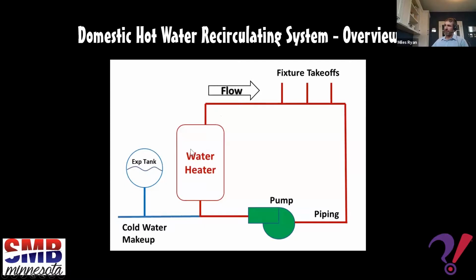Well, we have a water heater here that is creating hot water, maybe 140 degrees, 130 degrees, sending it out into this pipe. But now we'll create a loop. We have a piping loop with a pump on it, a recirculating pump, that basically makes sure we have hot water available in this piping loop at all times, because we'll have takeoffs from that piping loop to the various fixtures, the various showers, the various faucets. And we want all of the users of those fixtures to have hot water in a relatively short time frame. So that's the whole concept behind a recirculating system on a hot water system.